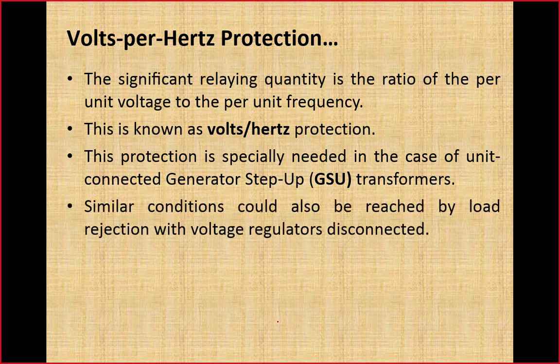And similar over excitation condition can occur for those transformers which are connected on the receiving end of long transmission lines in case of load rejection or in lightly loaded condition if voltage regulator is out of service, so that those transformers may also experience voltage beyond their rating, so that may result in overexcitation. So overexcitation protection must be provided over there as well. But remember, for those transformers, this protection will be done just by monitoring the voltage. Frequency will not be a variable of consideration.